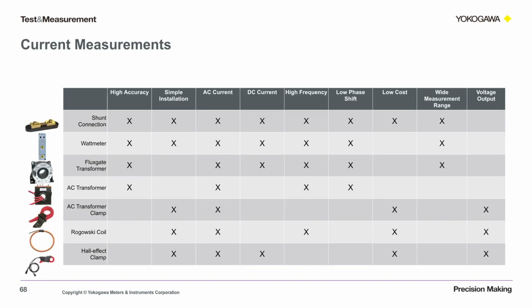There are a few more options for current measurements. The top two use a shunt resistor to make current measurements. Remember Ohm's law: voltage equals current times resistance. So with a known resistance, the shunt, current equals volts divided by resistance. Knowing that, we can calculate current. The wattmeter is what we use in power analyzers. There is an integrated shunt in the wattmeter that's actually compensated for temperature.